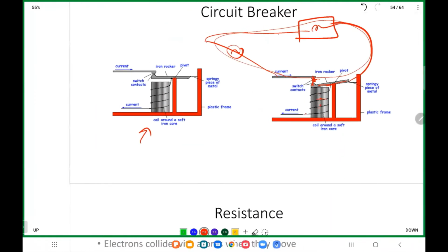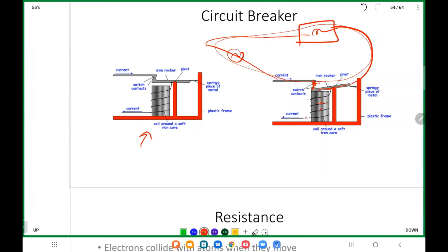Something happens, and when you go back to the circuit breaker, it becomes loose. This can happen because, although I showed a simple structure, there's actually a spring connecting these parts. Over many occurrences, you get two cases: sometimes a very bad short circuit with high voltage may destroy the electromagnet, though this is rare. But if a short circuit happens many times and the metal is attracted to the electromagnet repeatedly, the spring loses its elasticity and won't reconnect properly. That happened in my house many times—if it's a bad quality circuit breaker, the spring elasticity isn't good, though you can buy replacement springs.